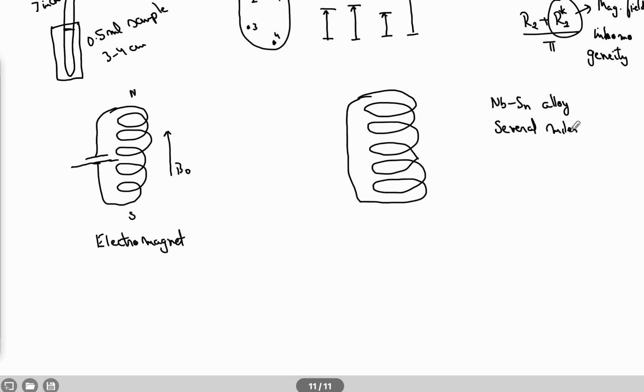So that means the length of it is huge. I'll share the exact height and all, like how big this turns out, but the length of the coil actually runs into several miles. Now, at the time of installation, there is a process called charging of the magnet. During charging, you supply electric current, and there is a circuit broken over here.